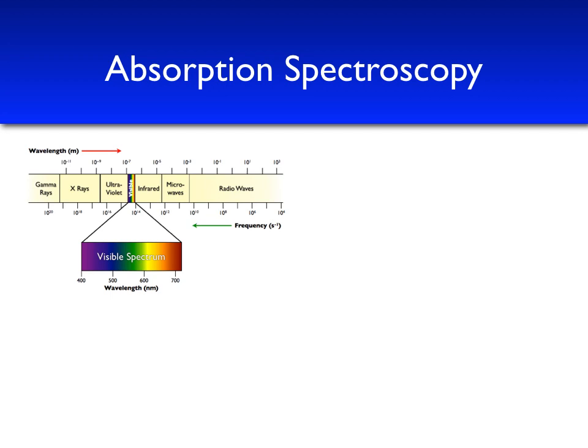To do this, we're going to have to take a spectrum. Most spectrometers work in very similar ways. Here's a schematic to explain how the SpectraVis Plus spectrometer works. In the SpectraVis Plus, and in all spectrometers, is a light source that gives off all the wavelengths of light we're interested in studying. For SpectraVis Plus, light is given off in a little bit of the ultraviolet to the near-infrared, so wavelengths that are slightly longer than the visible red light. This light passes through your sample holder, or cuvette.